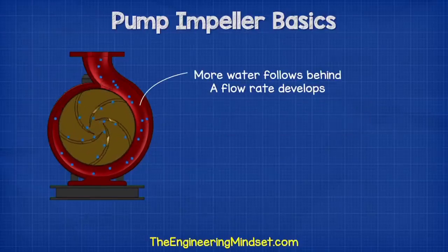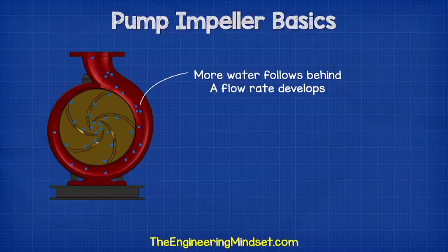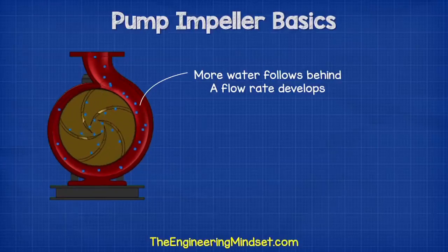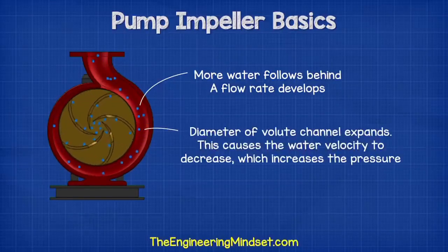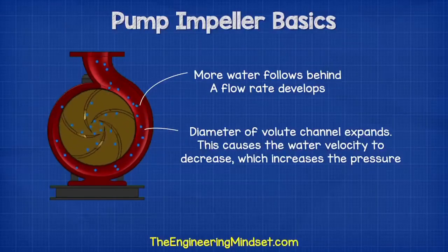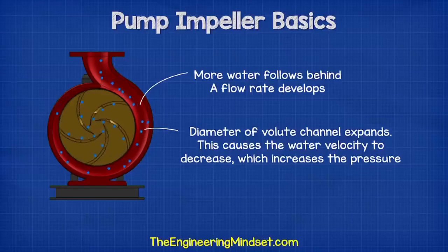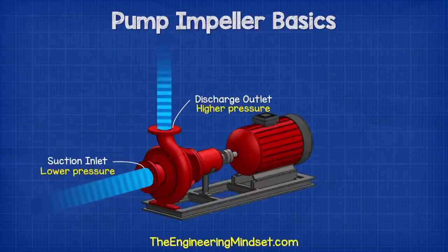More water follows behind and so a flow develops. The volute channel has an expanding diameter as it spirals around the circumference of the pump casing. As it expands, the velocity of the water will decrease, resulting in pressure increasing. This expanding channel therefore allows more water to keep joining and converting into pressure, so the discharge outlet is at a higher pressure than the suction inlet.